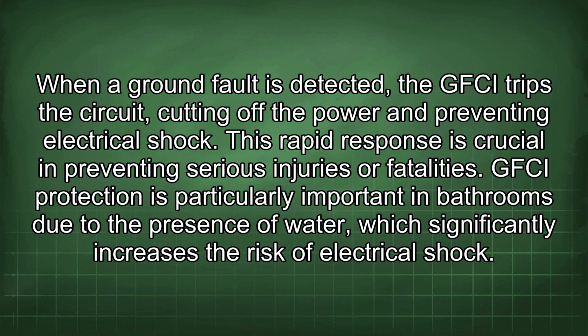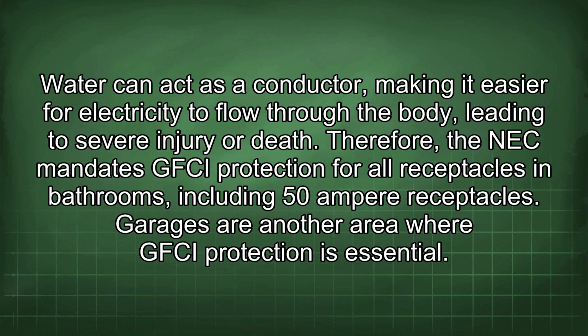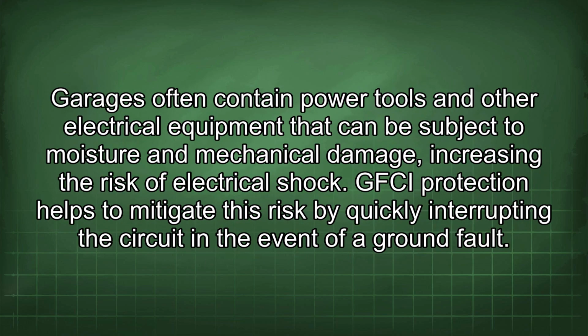GFCI protection is particularly important in bathrooms due to the presence of water, which significantly increases the risk of electrical shock. Water can act as a conductor, making it easier for electricity to flow through the body, leading to severe injury or death. Therefore, the NEC mandates GFCI protection for all receptacles in bathrooms, including 50 ampere receptacles. Garages are another area where GFCI protection is essential. Garages often contain power tools and other electrical equipment that can be subject to moisture and mechanical damage, increasing the risk of electrical shock. GFCI protection helps to mitigate this risk by quickly interrupting the circuit in the event of a ground fault.